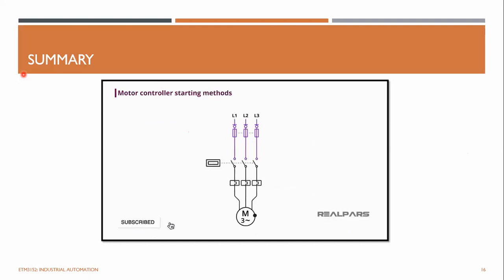The first starting type is the full voltage non-reversing motor controller. As the name implies, when the controller's single contactor actuates, this motor controller type, also known as FVNR, allows the full line voltage to pass to the motor.